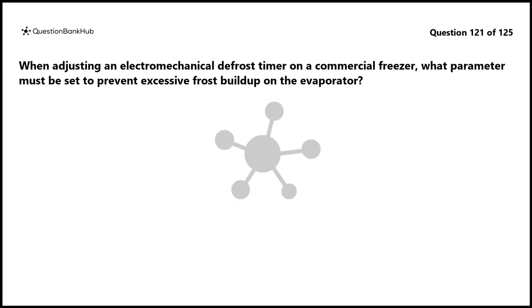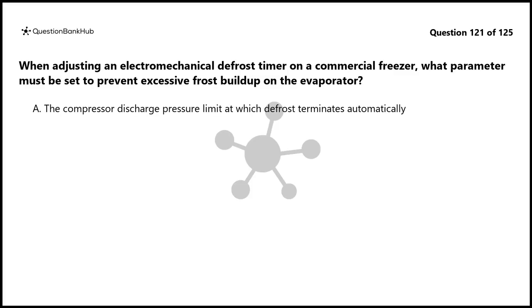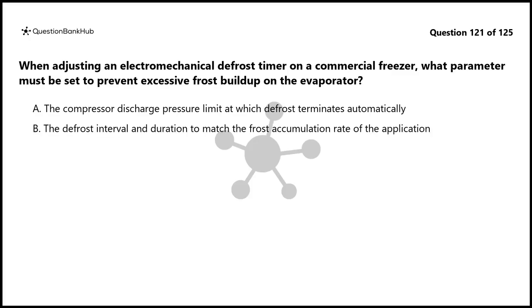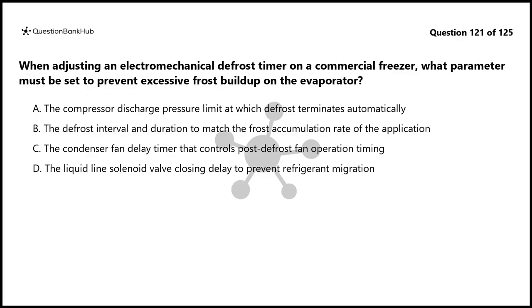Question 121. When adjusting an electromechanical defrost timer on a commercial freezer, what parameter must be set to prevent excessive frost buildup on the evaporator? A. The compressor discharge pressure limit at which defrost terminates automatically. B. The defrost interval and duration to match the frost accumulation rate of the application. C. The condenser fan delay timer that controls post-defrost fan operation timing. D. The liquid line solenoid valve closing delay to prevent refrigerant migration.